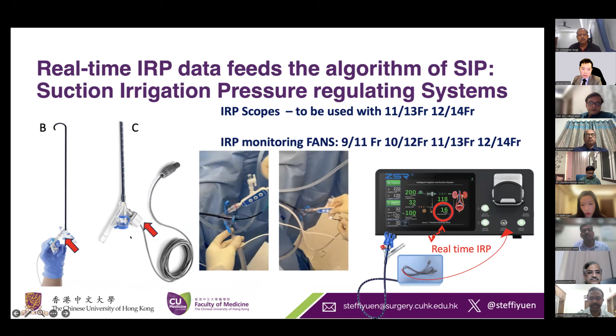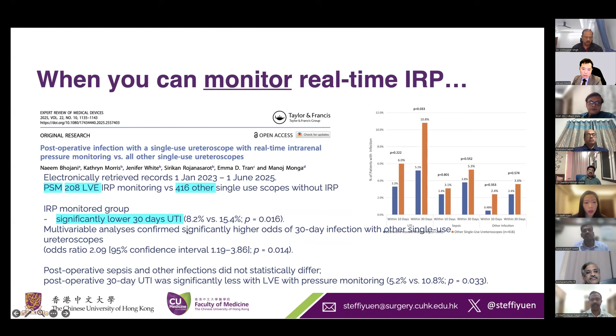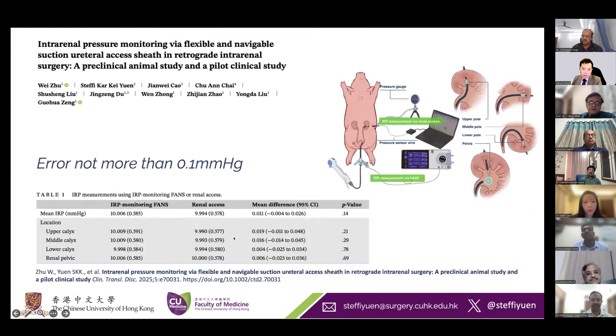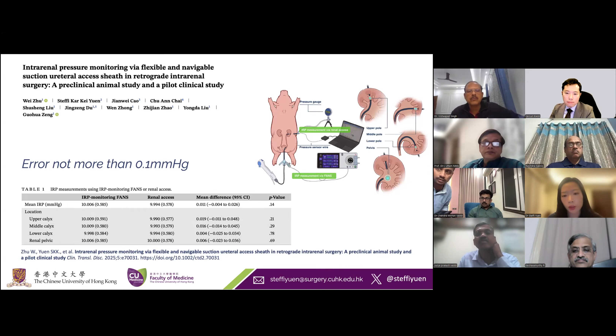When you can monitor real-time intrarenal pressure, actually it can lower 30-day UTI rates, as shown by this propensity score matched study. And if you look into animal studies that we've performed using one of the systems, if we place these IRP-monitoring FANS in the upper, mid, lower calyxes and the renal pelvis, the difference is not more than 0.1 millimeter mercury. So if you're worried that you're not putting the sheath at the correct position, it's actually not making that much of a difference in the pressure results.